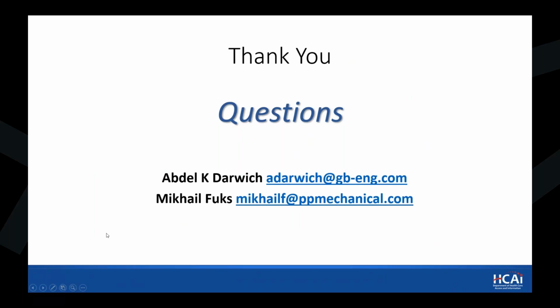First question: can we use a duct smoke detector to warn of wildfire conditions? Traditionally, most commercial duct detectors have not been tremendously effective at the kind of detection we talked about in this presentation. They typically focus on particle sizes larger than what we've discussed. That's spot on, I haven't seen it used effectively. Actually, the challenge I've seen in some buildings is that the code-required duct smoke detector gets triggered by wildfire smoke rather than by an actual building fire.